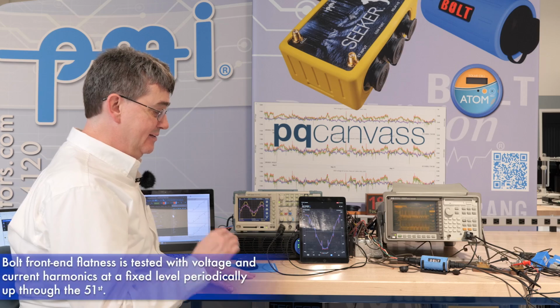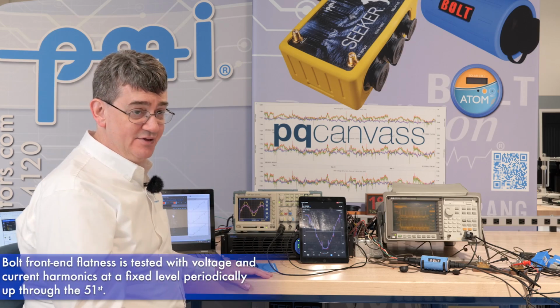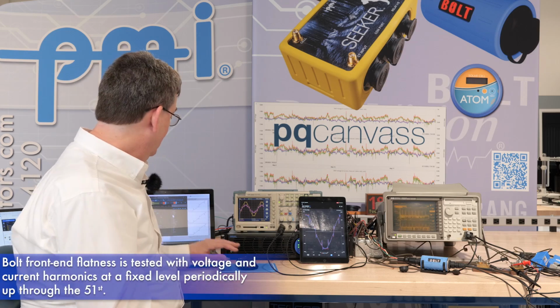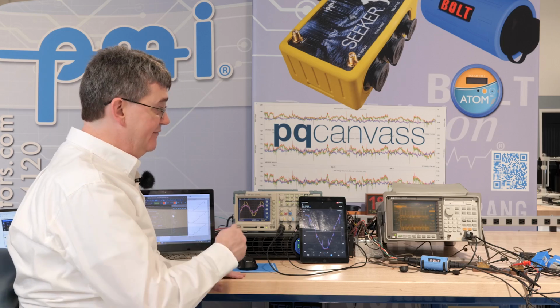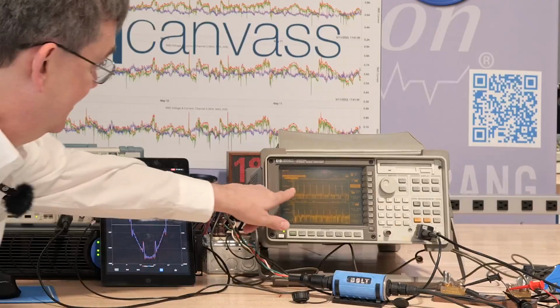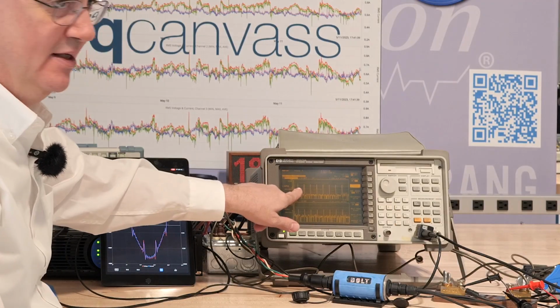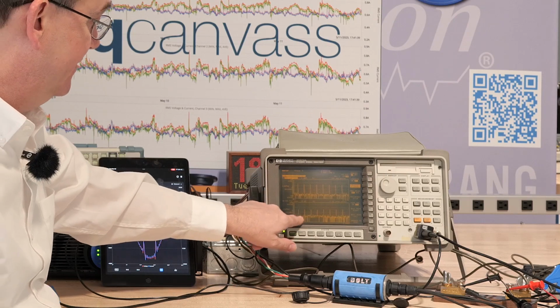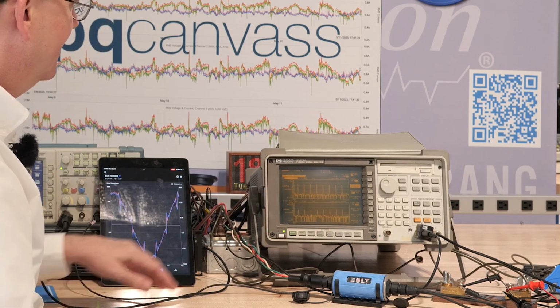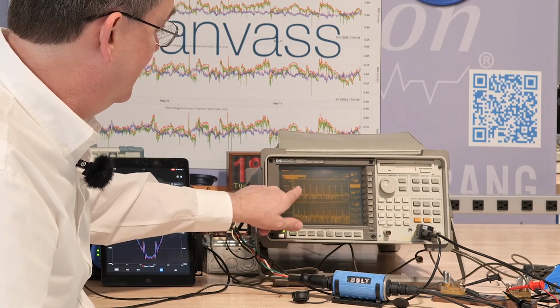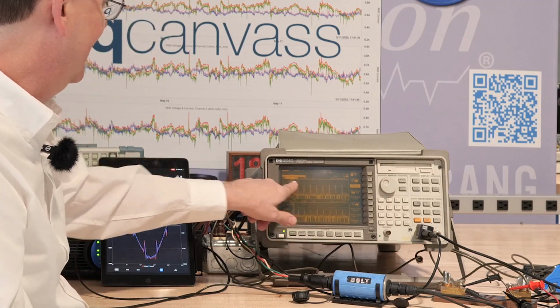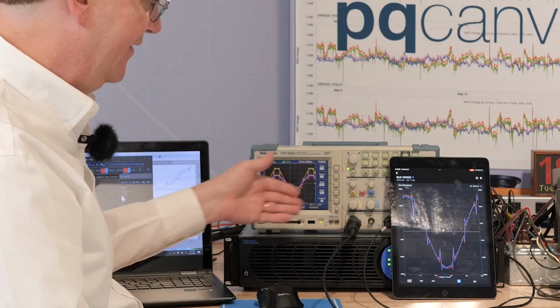So with our next test, we're going to test the flatness of the passband for the bolt to make sure that each harmonic, all the way up to the 51st harmonic, is the correct level. We have a special pattern where every 5th harmonic we have a line. These show exactly 5 volts in amplitude for voltage and the proportional amplitude for current. And you can see on the spectrum analyzer all the way up to 3 kilohertz, these are flat, and this is the special waveform that does this.